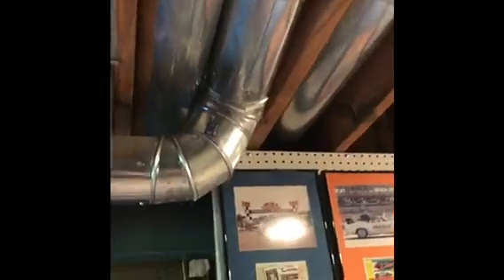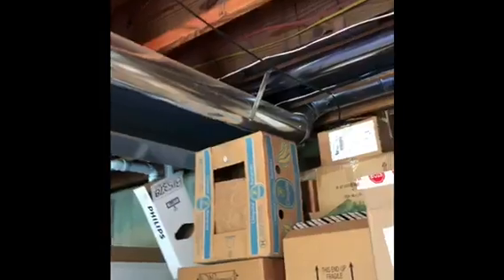Now, the ductwork down here on this side, we're going to put a damper in this 6-inch round that comes off. It's the very last run that comes off of that duct run. So we'll put a damper inside of that one, just a little manual damper, and then you have 2 6-inches that are stuck up inside of the joists here. What we're going to do is tape off every single one of the joints on these 2 6-inch rounds. These are the rooms that are not getting proper airflow to them because we're losing a lot of air running this 30 or 40 foot all the way over here to this master bedroom. So we'll tape all that stuff off and seal everything down.